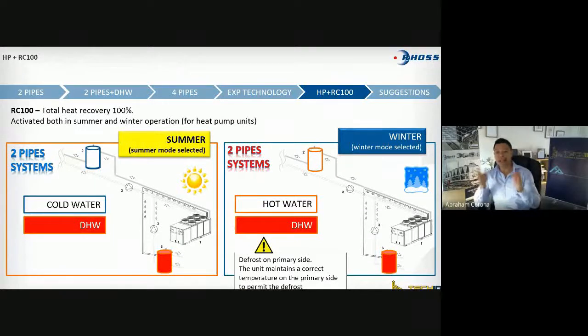The problem is, in an EXP system, you have independent circuits, independent cycles. The unit by itself can decide to do defrost on the primary or the secondary without any issue. Meanwhile, here is the warning you start to get in this kind of system. When you're running winter defrost on the primary side, the unit maintains a correct temperature on the primary side to permit defrost. So if the primary side is going to defrost, you're not going to have any issue. But if the secondary goes into defrost, you can be taking those temperatures even lower, and you're going to frost the fins more, and the system will stop.